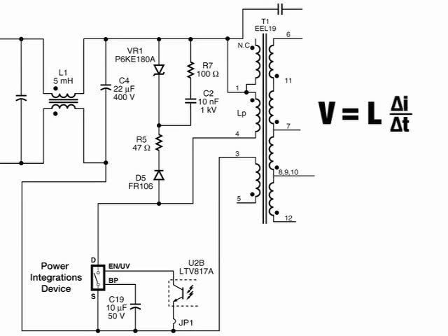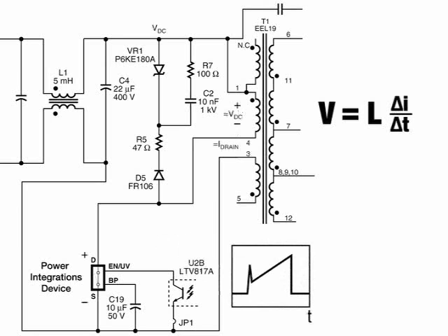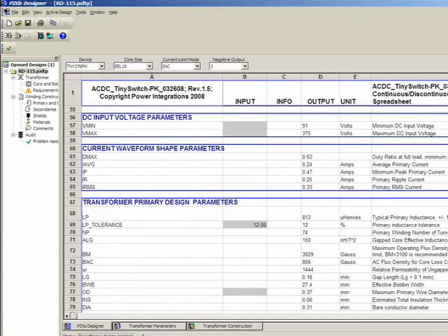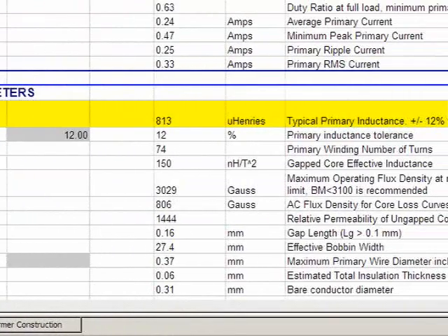When the MOSFET is turned on, the voltage seen across the transformer primary is approximately equal to the average DC bus voltage. The current through the inductor is the same as the drain current. Rearranging this equation, we calculate L as shown. Compare the value you calculated with the specified value in PI Expert. If it's outside the tolerances given, then contact your transformer manufacturer to resolve this problem.